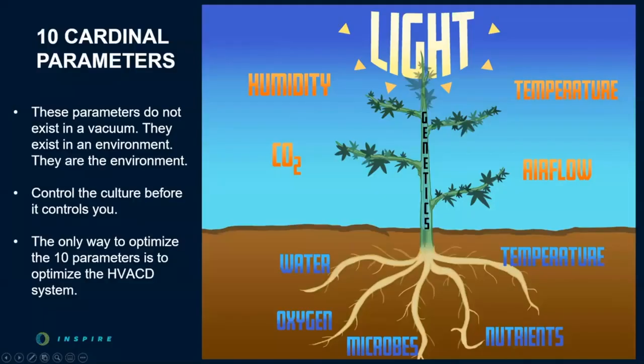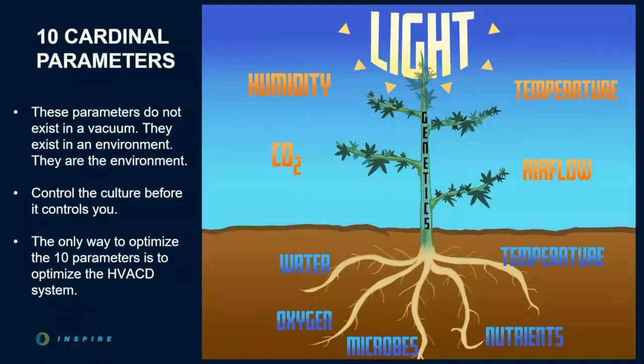The 10 cardinal parameters work synergistically, and all of them need to be optimized to ensure crucial KPIs are met, such as grams per square foot and price per pound. HVACD tells the full story of what environmental control for cannabis should do. There's heat load from the lights that needs to be accounted for, but it takes about twice as much work to dehumidify than it does to remove heat. Through the process of transpiration, plants act as perfect little humidifiers in cultivation rooms, and without proper modulating dehumidification, humidity rates and VPD simply cannot be maintained.